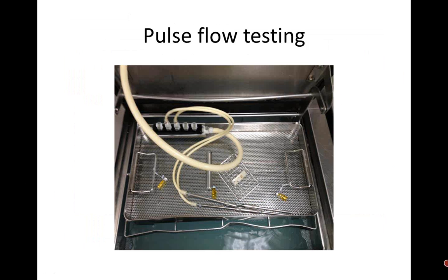This here again is a sonic. I'm checking with the SonaCheck, with also instruments, the TOSI that comes through, checking the pulse flow to make sure the pump is working and you're getting what you're supposed to get to clean blood off of stainless steel or whatever you're doing. This is a good way to check a sonic cleaner, all those factors of cleaning.